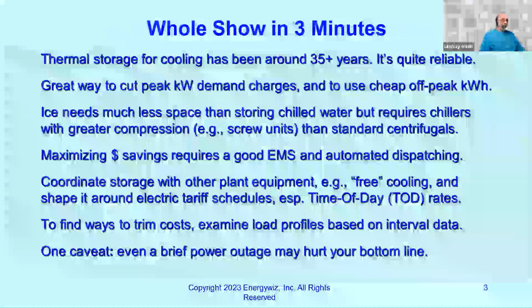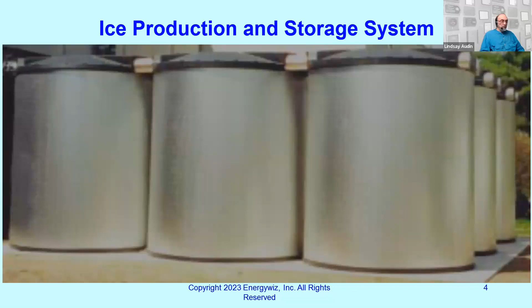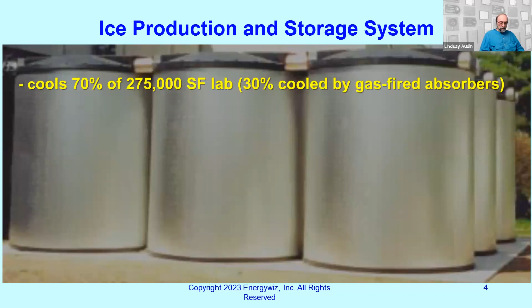So let's give you some background here. The system that I work with most was for one of my clients in Westchester County, which has had a thermal storage system for over 20 years. I've worked with others, but this one I was with and working on for over 20 years. Here's what it is. It's a 275,000 square foot laboratory. It does all kinds of testing on products. 70% of that space is cooled by the thermal storage system. The other 30% is cooled by gas-fired absorbers, once again, to avoid peak demand charges.